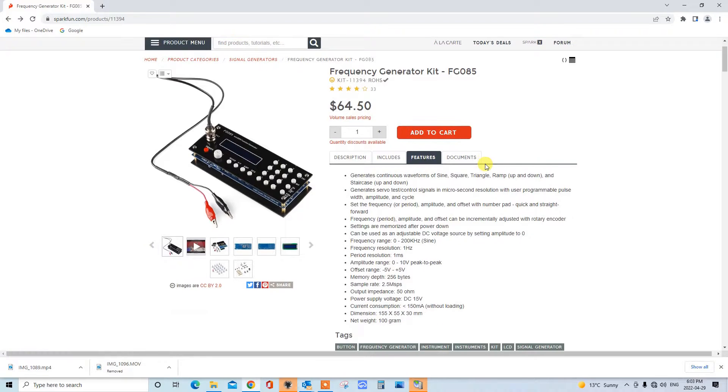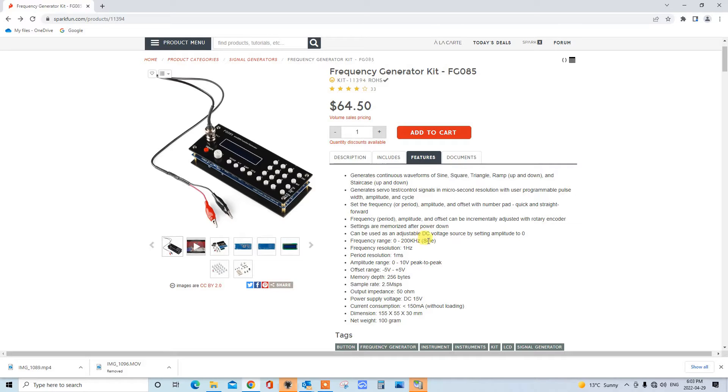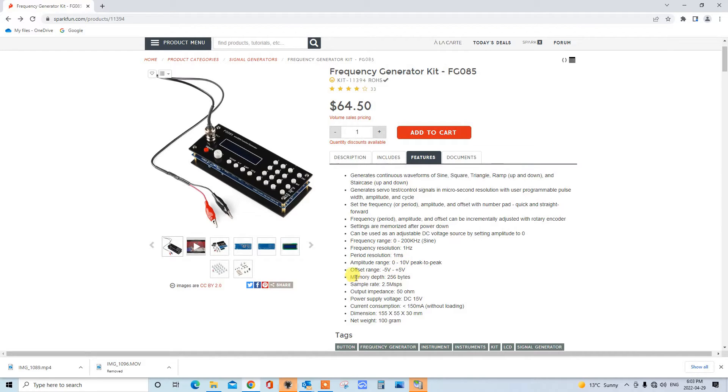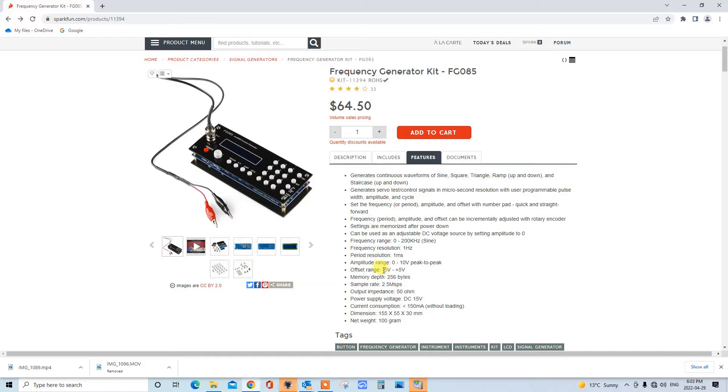You can see here that it has a range of 0 to 200 kilohertz, at least on the sine wave. Frequency resolution down to 1 hertz. Amplitude 0 to 10 volts peak to peak, and we can offset it with a DC voltage of plus or minus 5 volts. And there's some other specifications here.